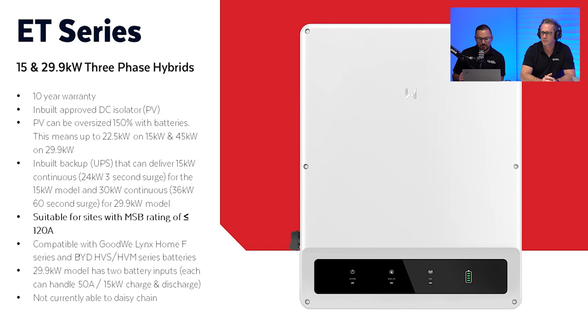As an example, if you have a customer that you want to achieve around 45 kilowatt of PV, rather than installing, say, a 40 kilowatt inverter capacity entering grid protection territory, consider putting a 29.9 kilowatt three-phase hybrid with a small battery. That'll allow you to oversize the PV 150% and still claim STCs.